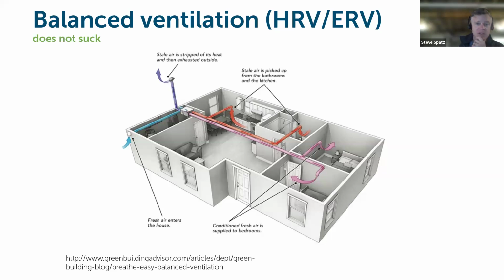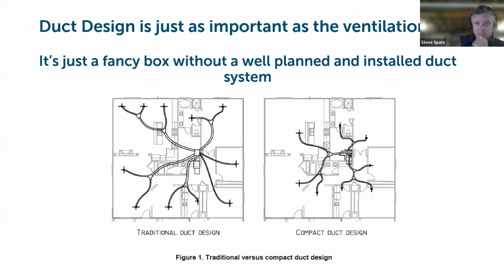So knowing what your specs are and what your options are for equipment that will perform under those conditions is critical. But again, that's just the performance potential of the ERV or HRV unit itself. It's a box with a fan and a blower motor in it, a heat recovery core, and 4 ducts coming off it. To create a system, you have to connect ductwork to it, distributing that air throughout the house. That duct system and that duct design is just as important as what that fan and that unit itself can do. So you really need to be accounting for mechanical ventilation as a system and as a design into the building at design stage.